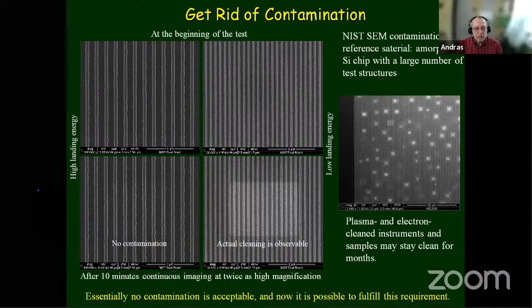Next slide, please. Very good. So this is, just please go back one, somehow I jumped two. That's about the sample. This was a sample that has been in storage, not used for years. The first image that you see is on the upper left. But if you dwell on the sample for 10 minutes, at twice as high magnification, in this case 200,000 times magnification at 1 kilovolt accelerating voltage, you will see a really ugly pattern forming due to the sample problem.